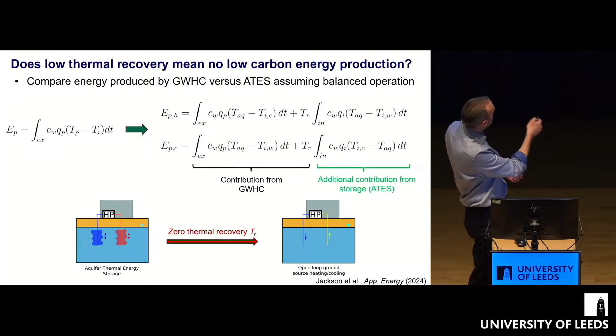So what you see is even if you end up with a thermal recovery factor of 0, you're just going back to a standard open loop system. You still get low carbon heating and cooling, you just don't get the benefits of storage anymore. So zero thermal recovery takes you from an ATES system to a classical open loop ground source system.